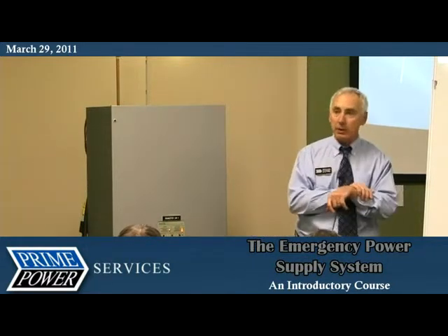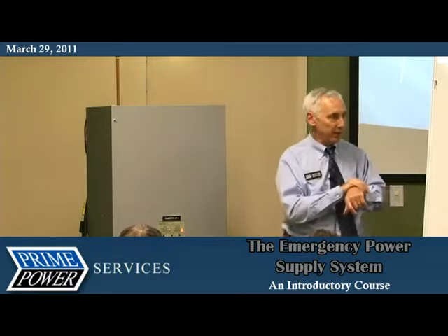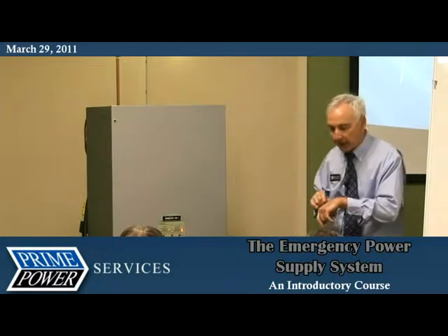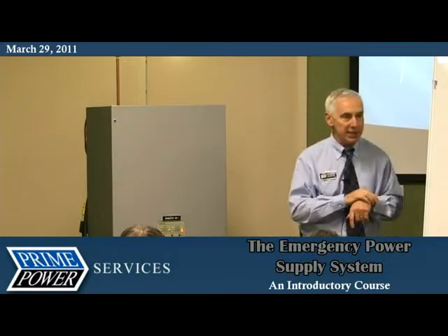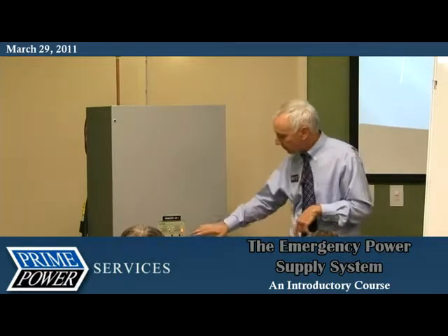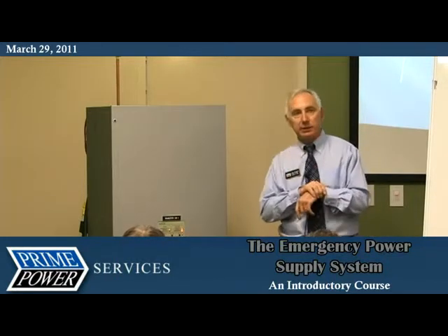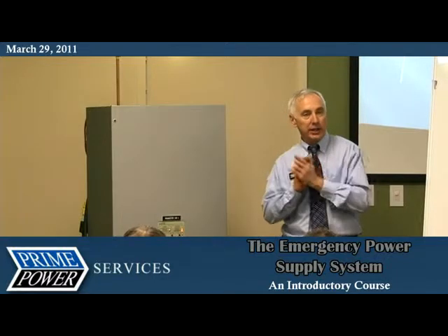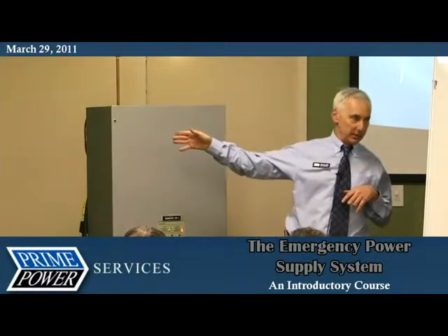Now that can be set at 0 seconds. You can just haul off and crank the generator if you want to. But in the hospital world, NFPA says that needs to be 1 second. So we wait 1 second. The power's still not there. We issue a start command to the generator.